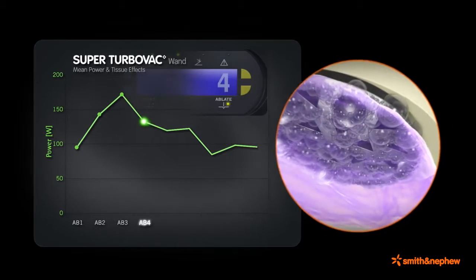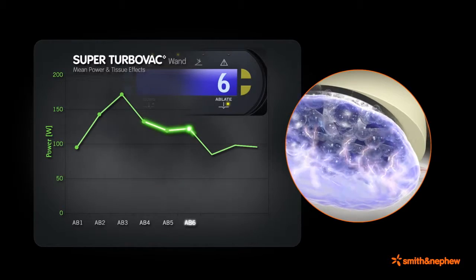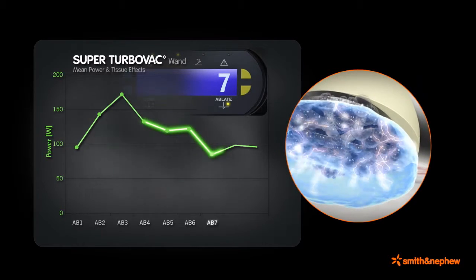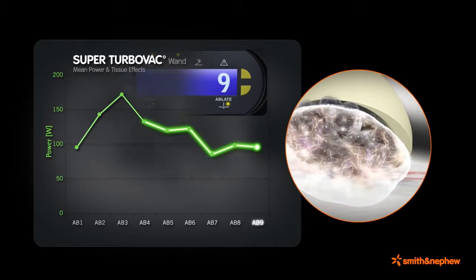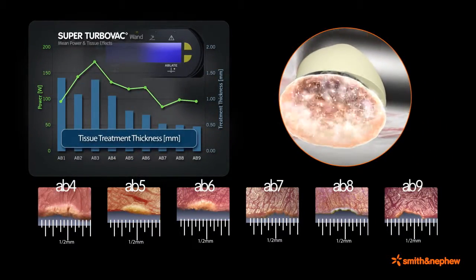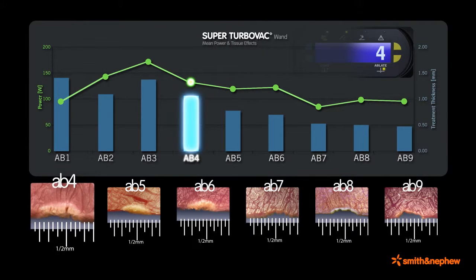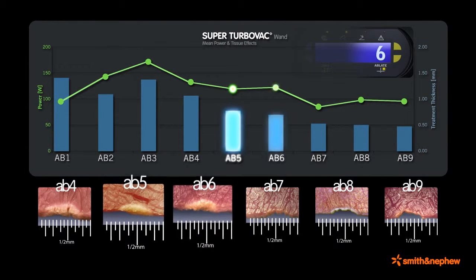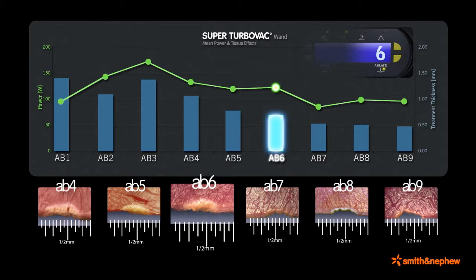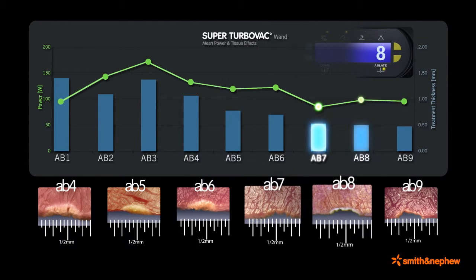When the controller setting increases, the plasma field increases in size and power decreases accordingly. When Smith and Nephew Coblation wands operate in ablation mode, the localized plasma precisely removes tissue with minimal damage to surrounding tissue.